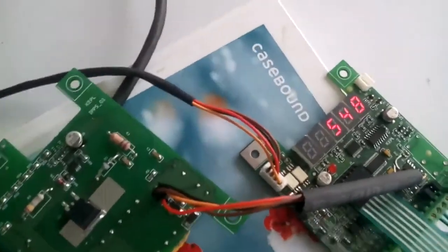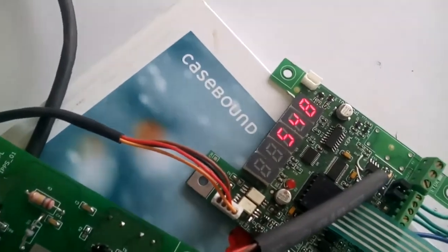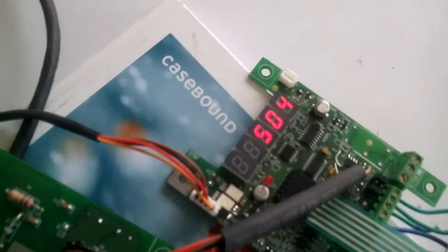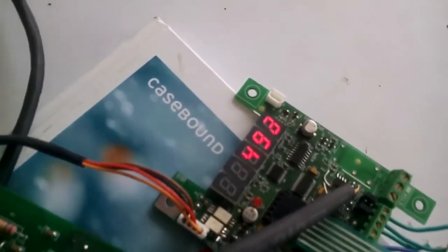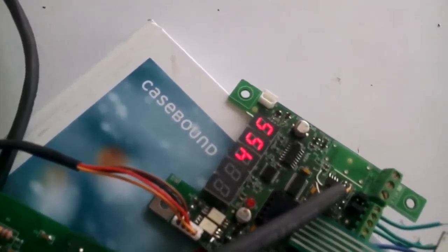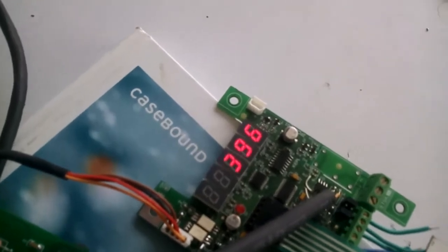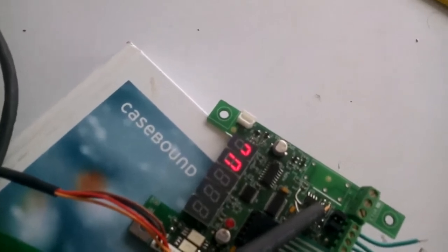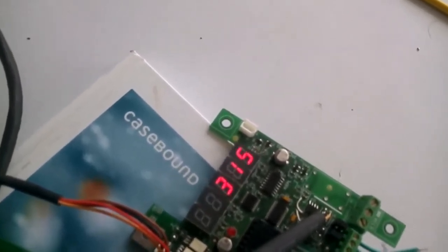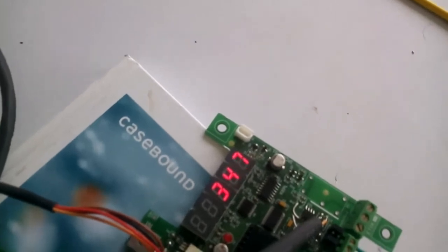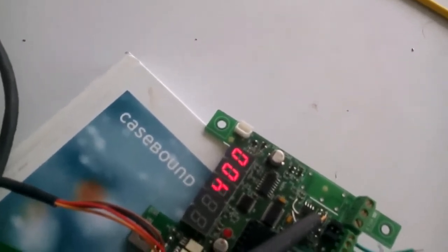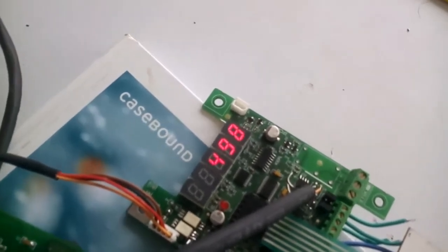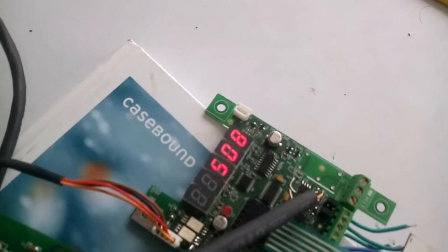So what we will do is lower down the voltage. The display shows the current DC bus voltage, so we will lower down the voltage. As you can see, it's in an under voltage condition now. Now if the voltage gets stabilized, the under voltage is clear. So UVCL shows the under voltage has been passed. The under voltage trip voltage is within the tolerance limit, so the under voltage test is passed.